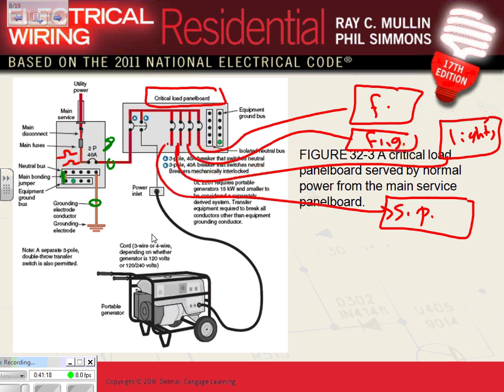Anybody knows why? The worst thing that could happen to you is you turn your generator and connect it to the grid without syncing it. Because the generator frequency, guys, and voltage will be at this level. And before you tie them together, we're going to talk about that next quarter, but before you tie them together, you have to start syncing until the two voltages and frequency line up like this. Then you throw the switch. Otherwise, it's equivalent, I have been told by the people who did it, to driving down 35W at, say, 75 miles an hour. There's no police there. And putting your gear in reverse.